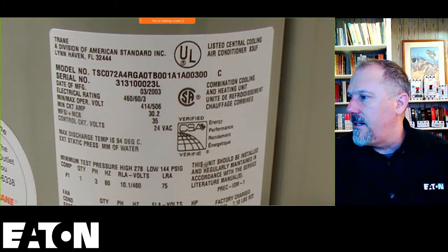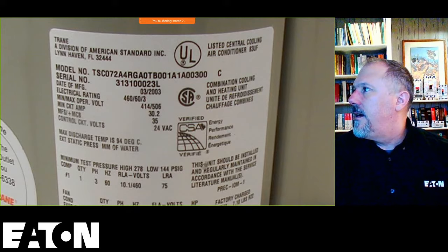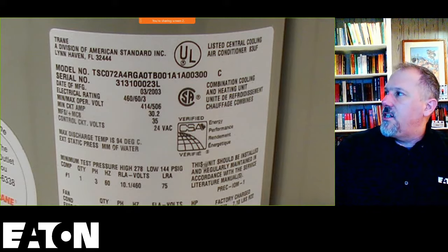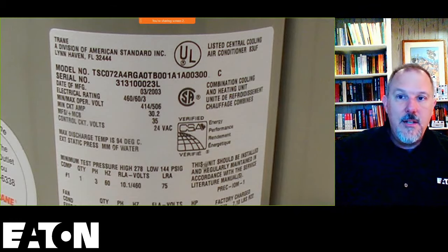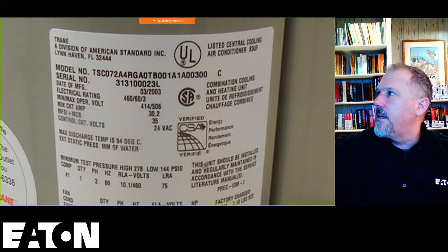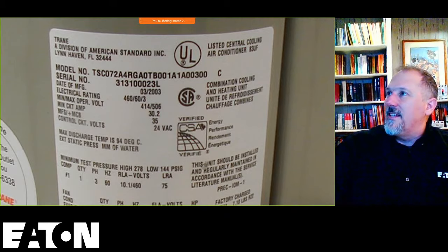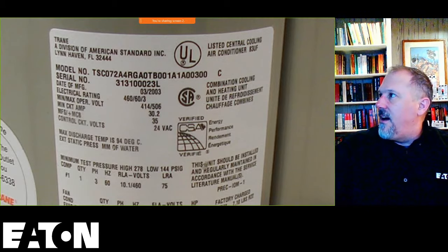I got a label right here. All right, so it does say combination cooling and heating unit. So I do have the word combination on there. If I read that, that would put me into listed central cooling air conditioner, so that I see what the listing mark is. I've got my listed, and it does say, but this is a CSA mark, says a combination cooling. So if it's not CSA listed, let's take that off.